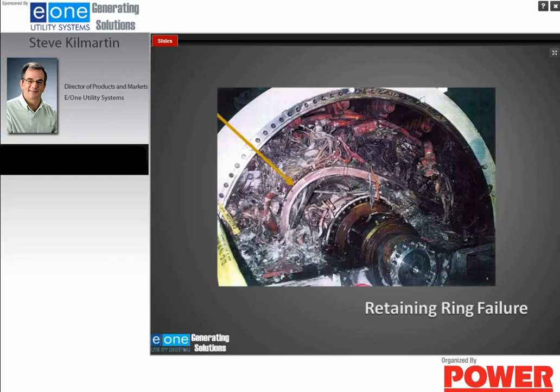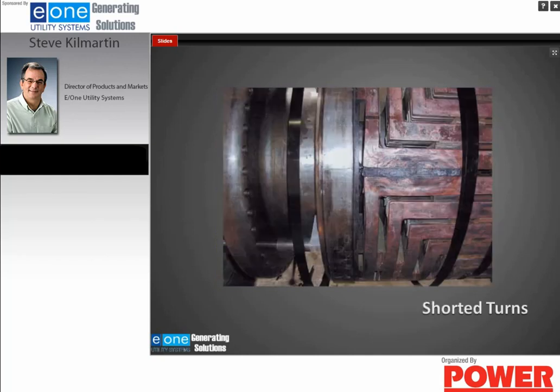This is what happens when a retaining ring lets go. This is not a pretty picture. This is what an insulation breakdown would look like in a generator. This is actually the rotor turns that are located underneath the retaining ring. Again, there's a paper written by Don Albright of Generator Tech that goes into great detail on the effects of moisture on turns in the rotor.